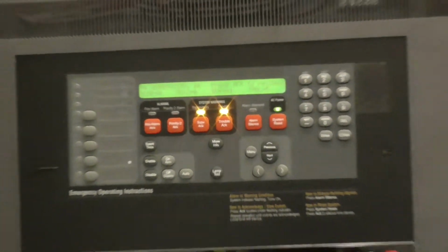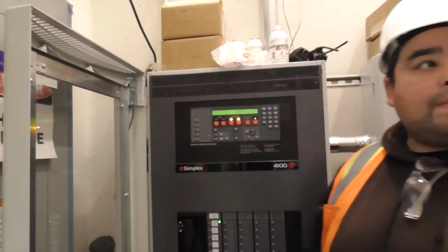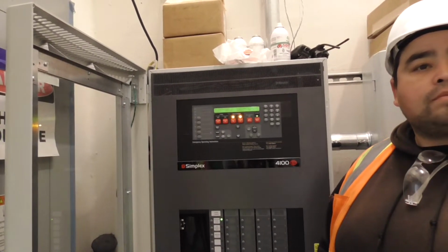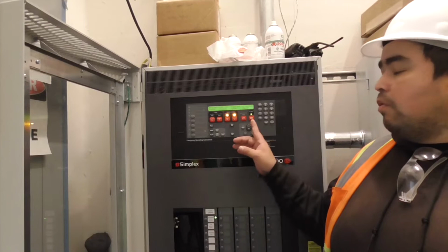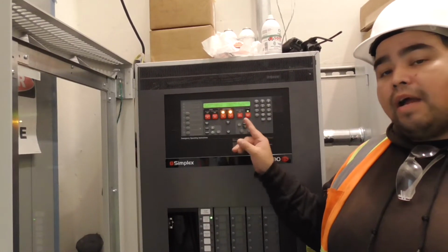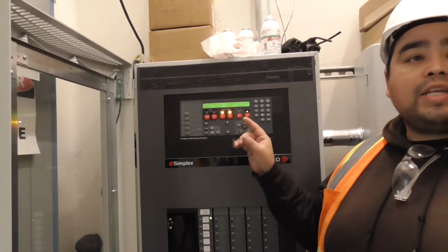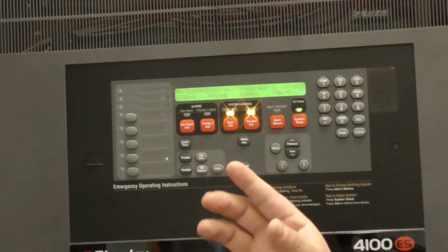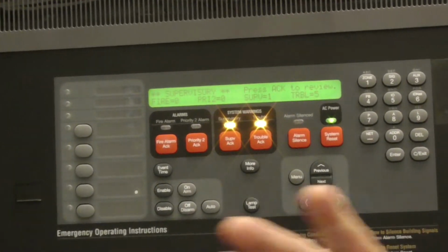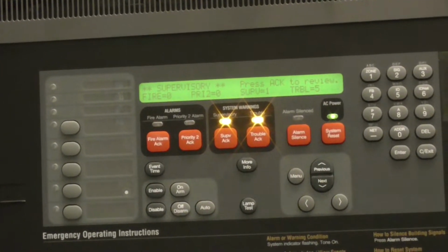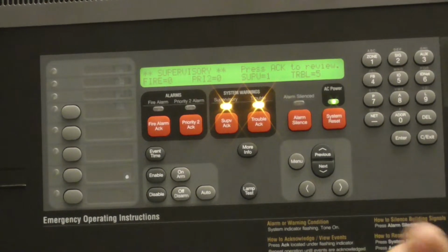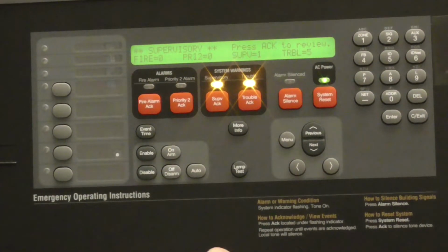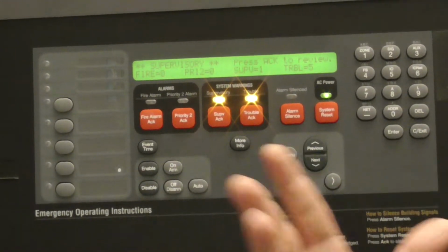Does that trigger an evacuation of the building? No. So it's similar to the supervisory, in that it only affects the suite or the apartment. That's correct. The only thing in the units that will set it into general alarm are the heat detectors. For sequence of operation, all heat detectors are general alarm. Yes. Other than that, any other event inside the room is localized to the room. Smoke spreads out and gets into the corridor, and then it'll go into general alarm. Yep. And the whole building will go off and evacuate everybody.